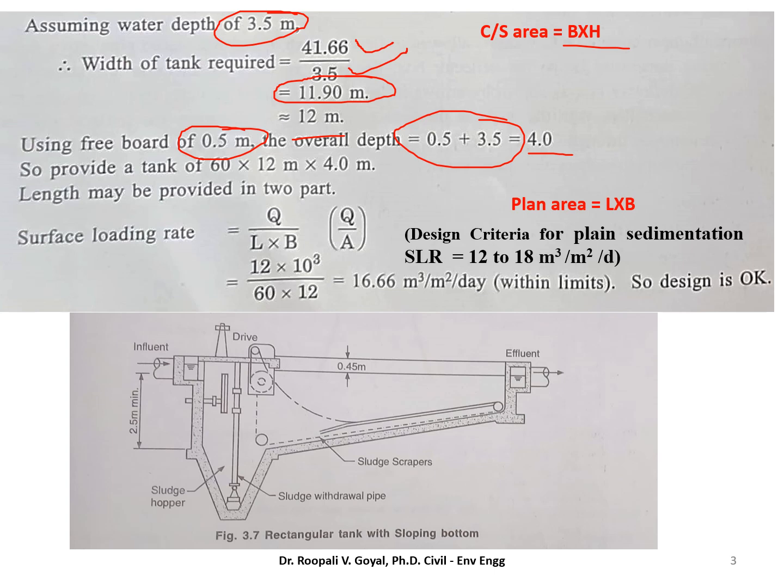So ultimately the tank size is 60 meter length by 12 meter breadth by 4 meter overall depth. And length may be provided into 2 parts. Now always we are checking the surface loading rate. And surface loading rate is given by Q upon A. And we call it A because the surface loading rate is related to your vertical velocity.